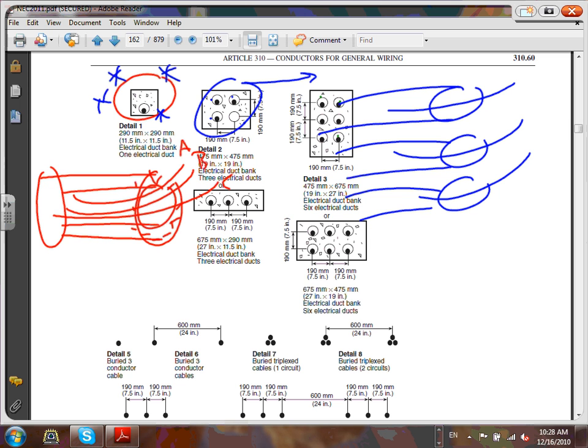The single conductor cable is a good application if you have a 2000 kcm cable. I mean, anything higher than 1000 kcm would be a great application for single conductor cable, medium voltage, because you just get too big as a conductor. If anybody wants to, check Southwire. They have an MC cable, medium voltage MC cable, and see what the largest size multi-conductor is that they make. Single conductor, I know that I have one in my office right now, 115,000 volt, 2,500 kcm. That's not even in any code book. 2,500 kcm. So they make them custom design for any need, and that would be feeding cities.